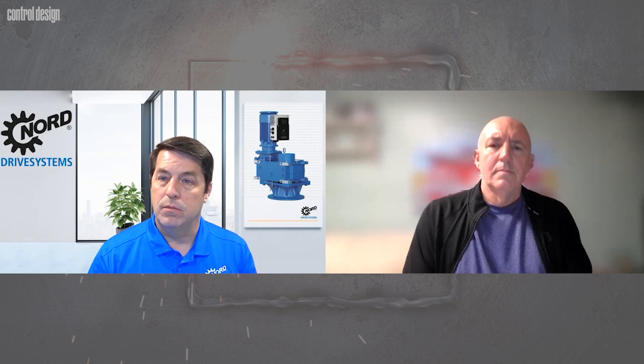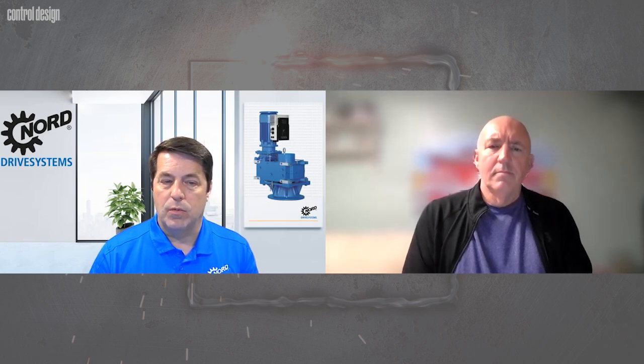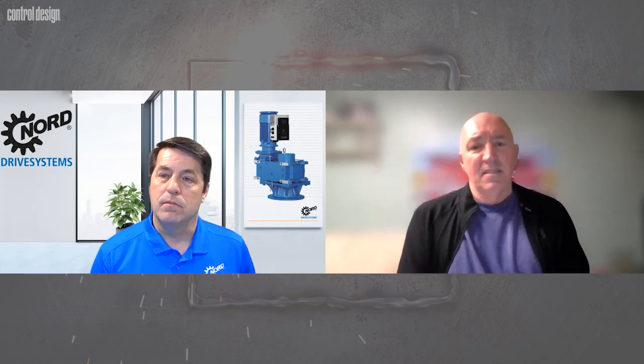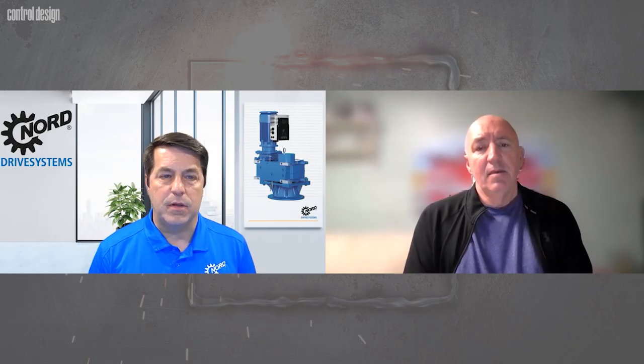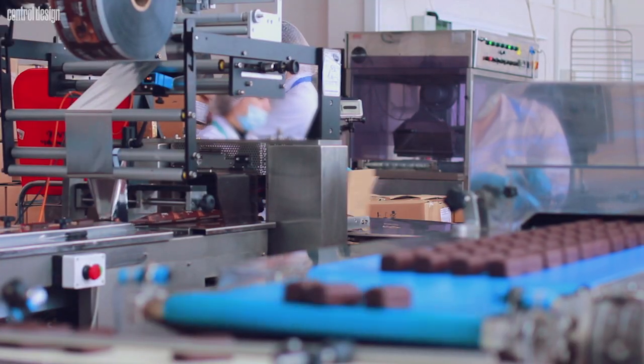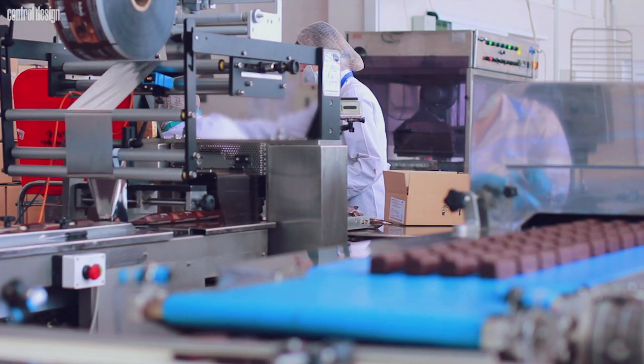How accurate can we be? How fast can we be? We can definitely be repeatable, for sure. So that's where the decision making for servo versus AC induction motor comes down to: how fast do I need to be, and how accurate do I need to be? If you can sacrifice speed a bit, we can get you very accurate because we know that positioning from our encoders that we read into our VFDs. So the application dictates what is possible, essentially. For sure. Right. Yeah, maybe indexing applications in food and bev or something like that. Maybe not, but certainly in the packaging part of that food and bev industry, for sure, it's something to consider.